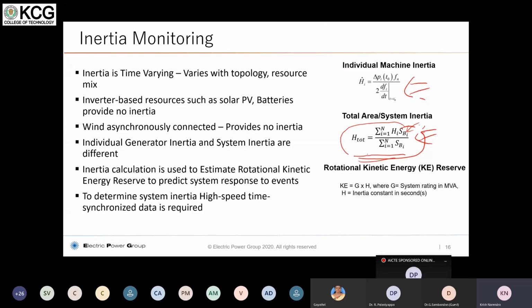This is what we are talking about: it varies because of the various dispatches that happen in a system and the non-support of inertia from the renewables. All these things have to be considered. And inverter-based systems, as I said, don't support inertia, or provide no inertia. And wind, even though they have rotating mass, cannot support inertia, because the very way it is designed as of now is not to support inertia.